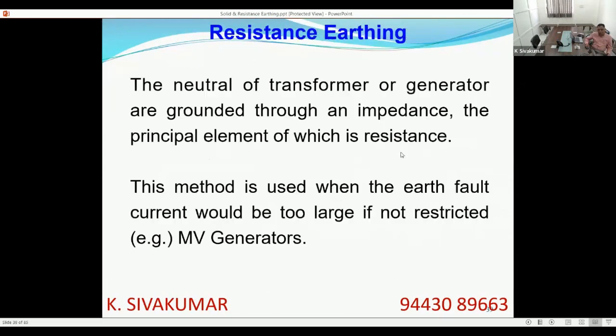Now, in resistance earthing, the neutral of the transformer or generator is grounded through an impedance. The principal element of that impedance is resistance. So, where to use this resistance earthing? This method is used when the earth fault current is to be restricted. If you solidly earth, the earth fault current is unrestricted, there will be a huge flow of earth fault current. If one wants to restrict the earth fault current, one may have to go for resistance earthing.